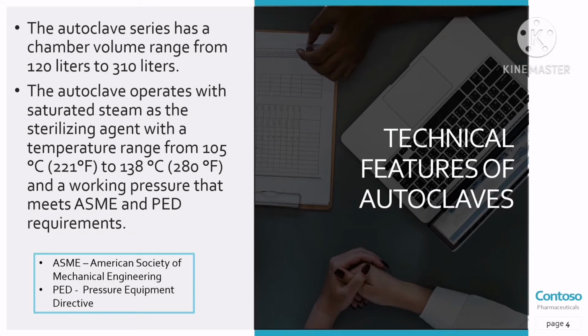The next slide is technical feature of autoclave. The autoclave series has a chamber volume range from 120 liters to 310 liters. The autoclave operates with saturated steam as the sterilizing agent with a temperature range from 105 Celsius to 138 Celsius and a working pressure that meets ASME and PED requirements. What is ASME? ASME is the American Society of Mechanical Engineers, and PED is the Pressure Equipment Directive.